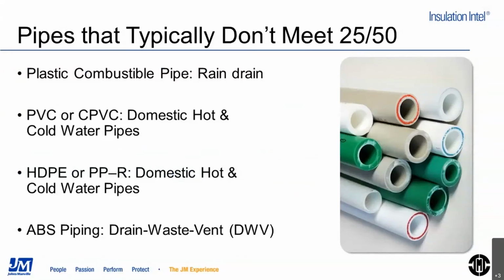So as mentioned, there's quite a bit of pipes that can be in the plenum space. So let's talk a little bit more about the pipes that may not be meeting the requirement of 25/50. There are actually quite a few pipes and a few uses for them. Most often, the combustible pipes will be used for rain drains, domestic hot and cold water, also the waste and vents. And the materials most often used are PVC, CPVC, high-density polyethylene, polypropylene or cross-linked polypropylene, so that's PPR, as well as ABS piping.